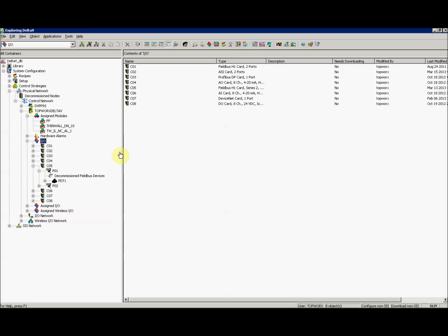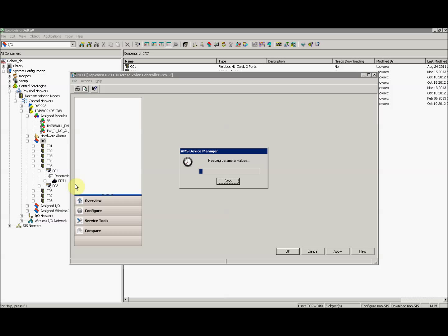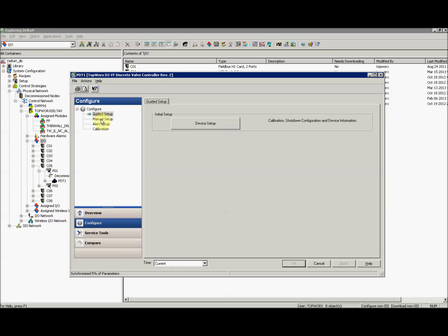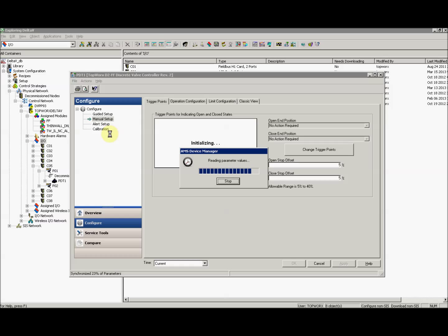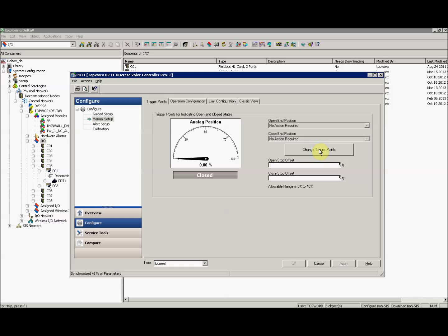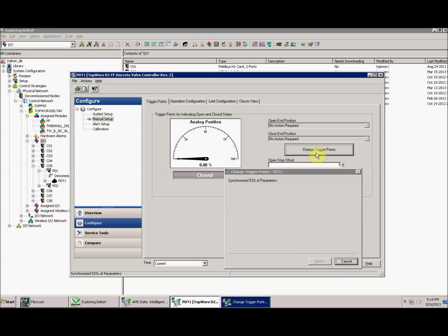If the device is commissioned, you can stroke your valve between open and close through AMS. To do that, right-click on your device, select Configure, now select Manual Setup. Click the button Change Trigger Points. Now first, it's going to put your device out of service, both the transducer and the resource block. So you can go ahead and click Next.